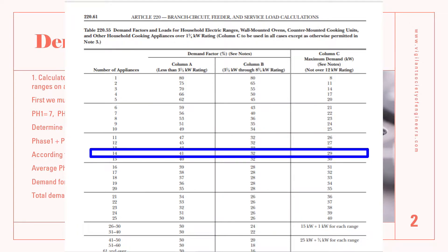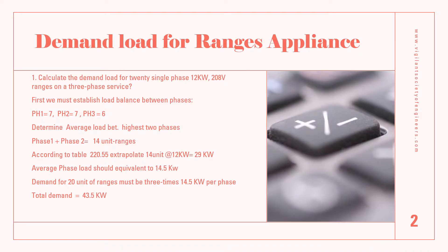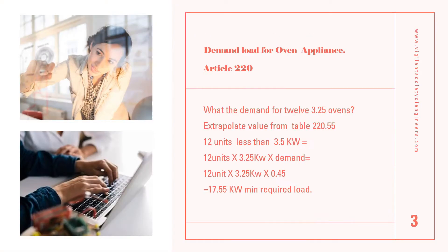That value is taken from column C and it is 29 kilowatt. The average kilowatt load is then determined for each phase by dividing that value by 2, so per phase it's 14.5 kilowatt. To find the total demand for the 20 units, we multiply 14.5 kilowatt per phase by three phases, giving us 43.5 kilowatt.